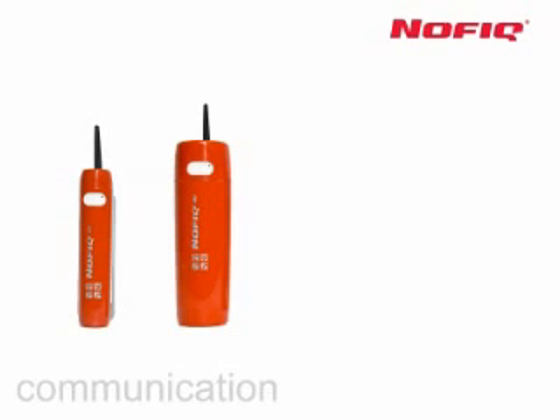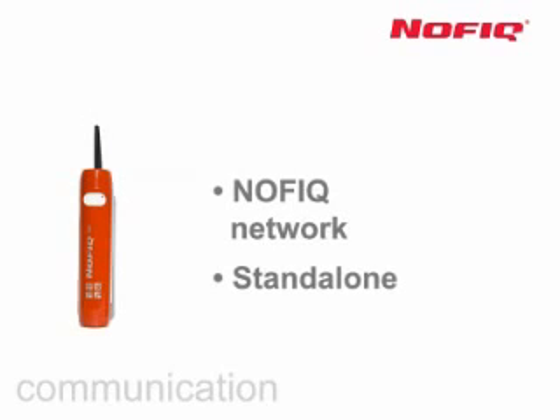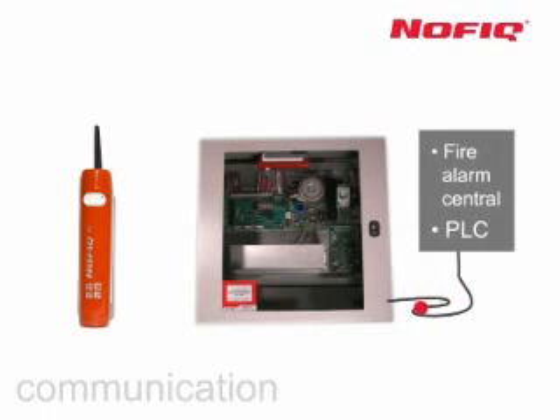The NOFIQ 20 and NOFIQ 80 can be configured in two ways: in its own wireless NOFIQ network, or as a stand-alone system. A stand-alone system is enough to secure a single switchbox; the alarm is then initiated via a potential-free contact that connects to an existing fire alarm and/or alarm system.